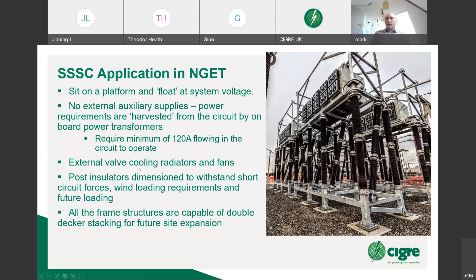Here we're showing a typical installation. One of the key points to notice is that we talked about having a parallel bypass. When we install these, here are the triple SCs, but in parallel with this we have a mechanical bypass as well. Within each of these modules there is the vacuum switch and SCR, as we described before, but within National Grid we've also decided we want a mechanical bypass so that we can put the circuit back into service if we need to take these out for any reason. We're also keeping these within the substation because of the wireless communication, and if we need to do any maintenance or intervention, we want to be able to do this with minimal impact on the system, so we can take this out and then put the circuit back in play.